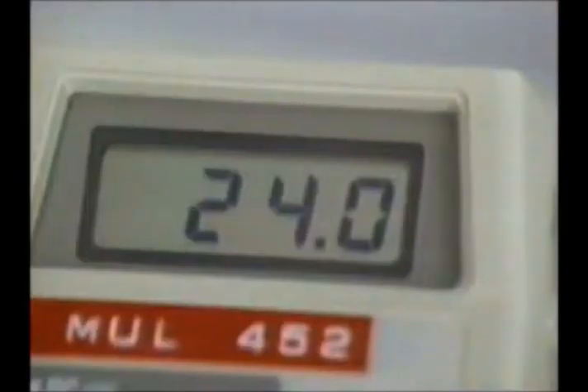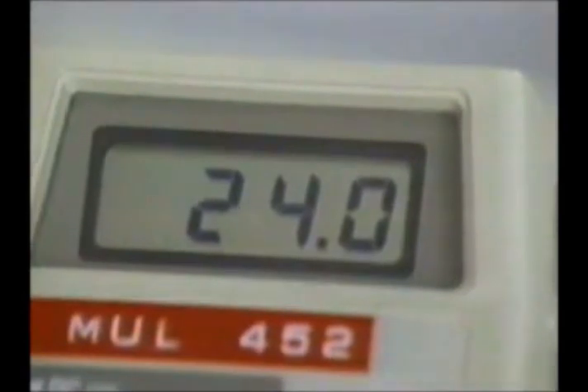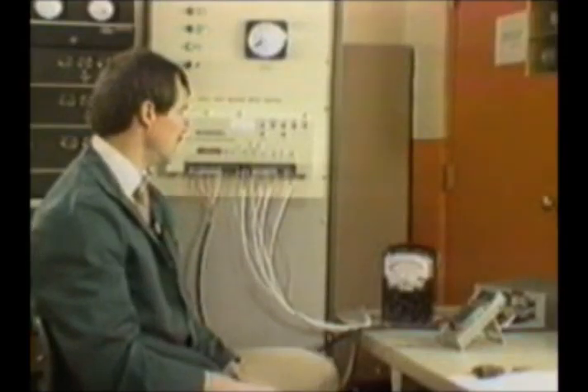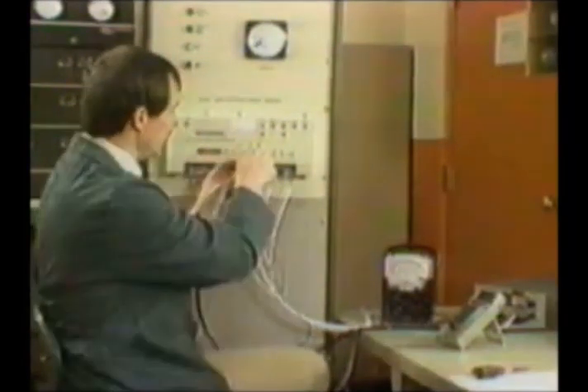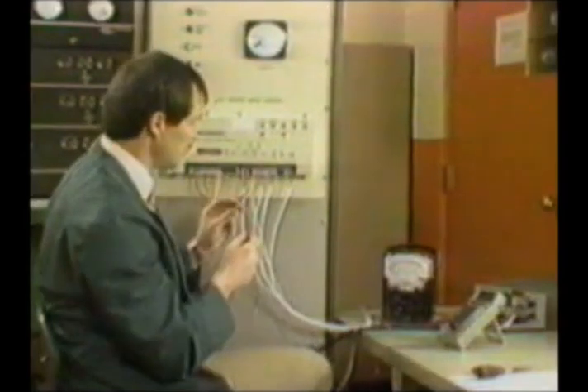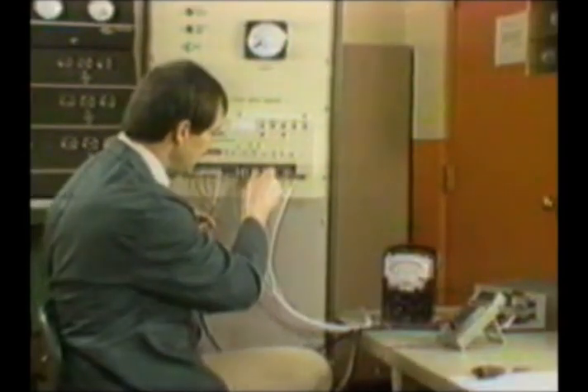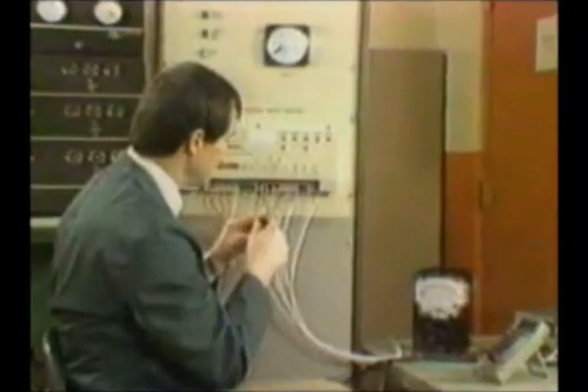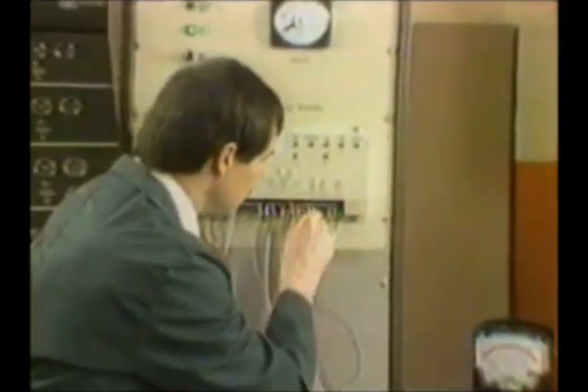My digital meter reads right around 24 volts. So I can run anywhere from 20 volts to 45 volts DC, so I'm just going to leave it set there at 24 volts. The next thing I need you to check out, I want you to put the positive side of your meter on terminal 20, the negative side on terminal 22.